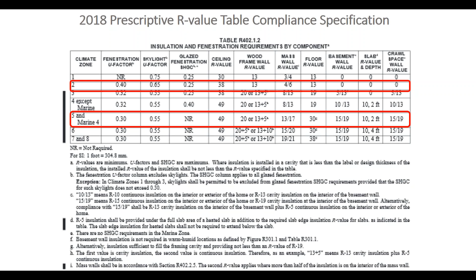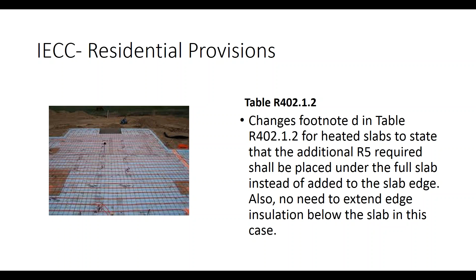But the mechanical code always required that if you had a radiant slab, you had to put an extra R5 under the entire slab, and that was never in the energy code. So we took that requirement out of the mechanical code and brought it into the energy code, so that now if you heat your slab, you put the R5 under the entire slab, and you don't have to add the extra R5 to the side of the slab in addition. That's a change to the code because there was always either a conflict or a lack of correlation between the two codes, so we just put it all in one code.